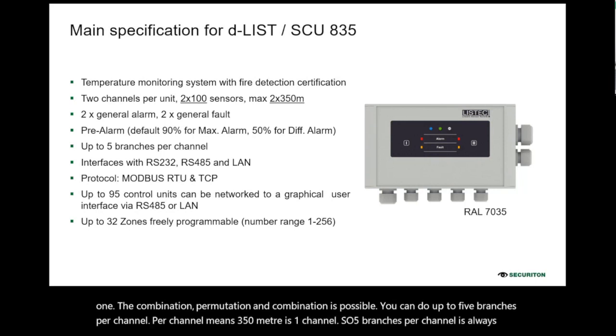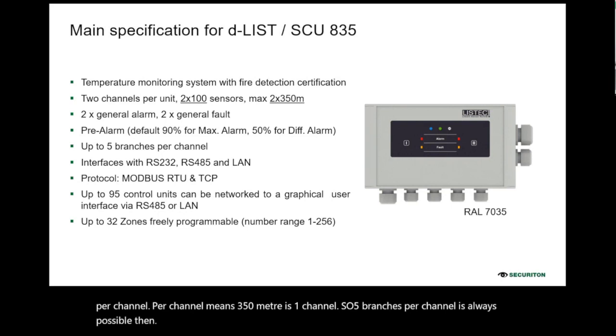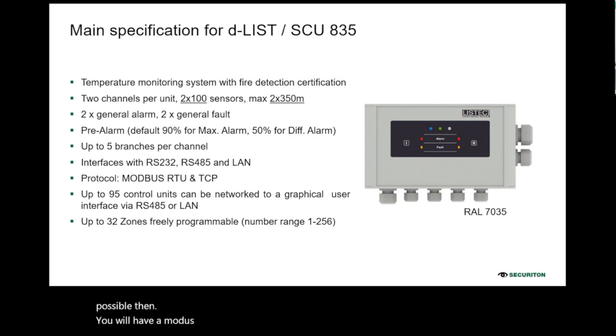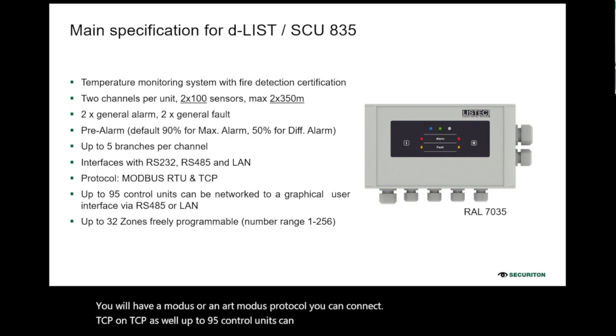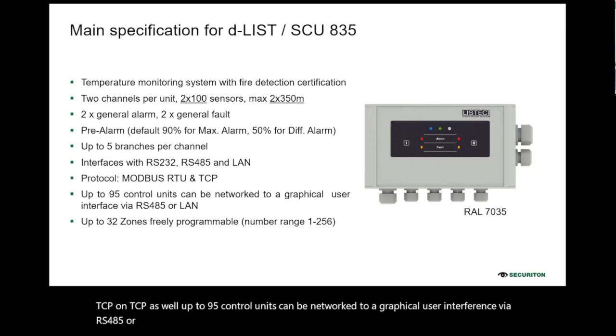Then you will have a Modbus protocol. You can connect Modbus TCP as well. Up to 95 control units can be networked to a graphical user interface via RS485 or LAN, and up to 32 freely programmable zones are possible with this controller.